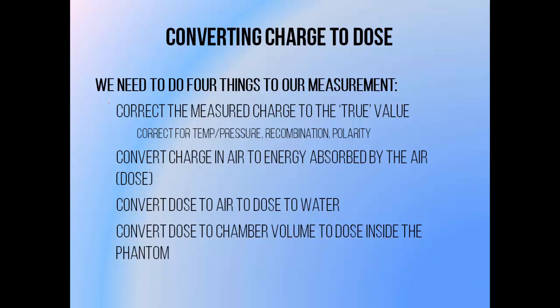Getting a measurement of dose to a point in water from an ionization chamber charge reading requires a few steps. The first is to correct the measured charge to a value that more closely reflects the amount of radiation hitting the chamber.